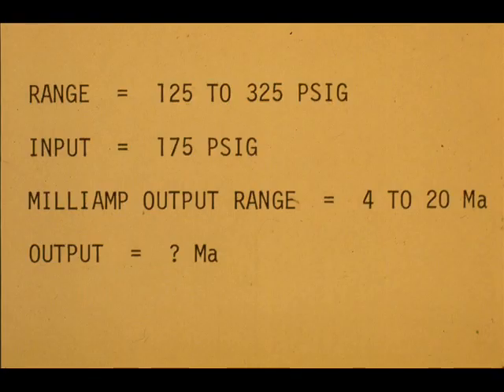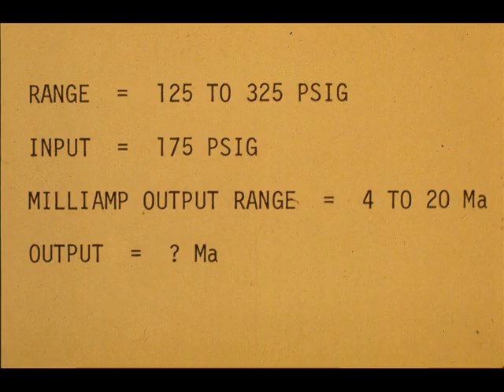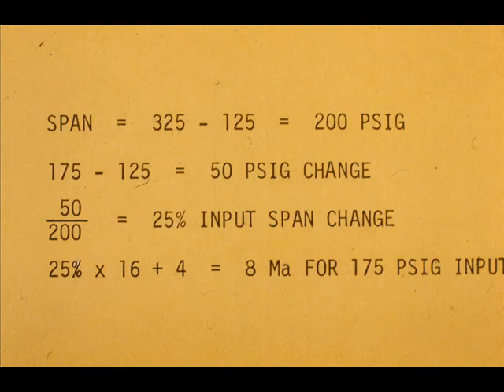Take the 125 to 325 PSIG range, for example. Assume an input of 175 PSIG to a 4 to 20 milliamp transmitter. What is the correct output? The span is 200 PSIG. An input of 175 PSIG is 25% of the input span. 25% of the 16 milliamp output span is 4 milliamps. Add this to the 4 milliamp starting current, and we have 8 milliamps as the answer.